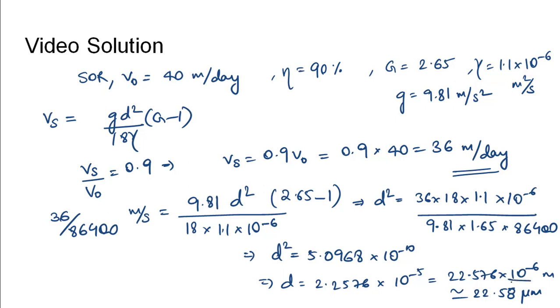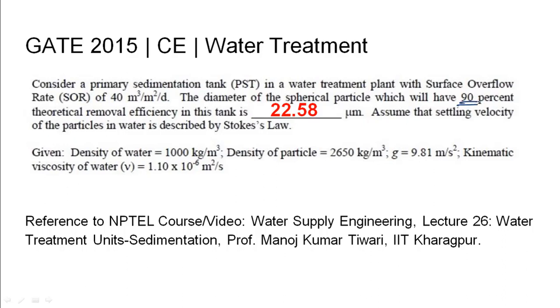This equals 22.58 micrometers. The diameter of the spherical particle which provides 90% theoretical removal efficiency is 22.58 μm.